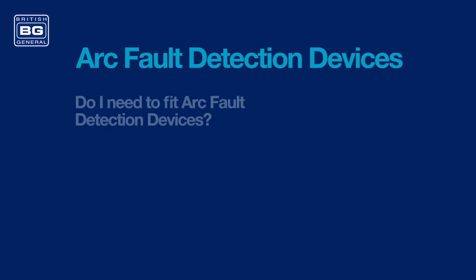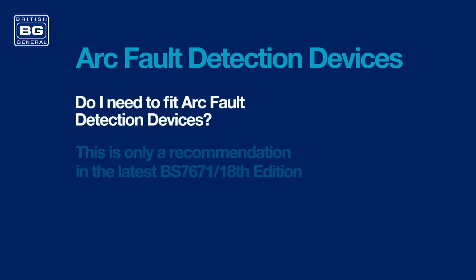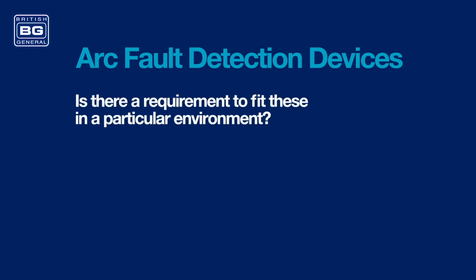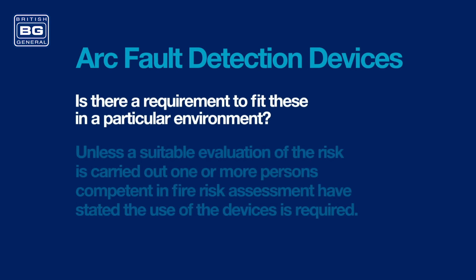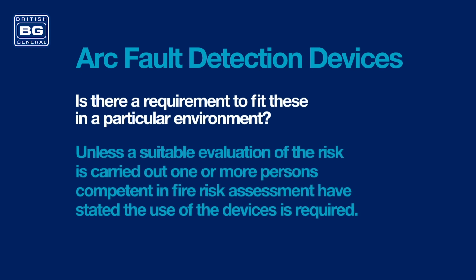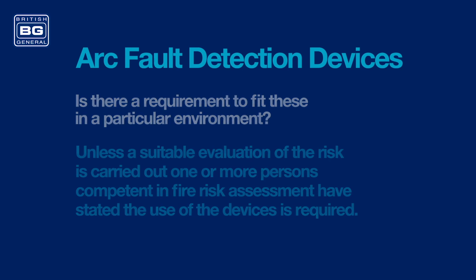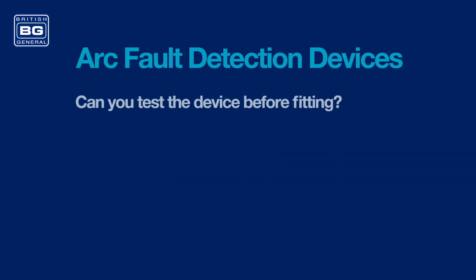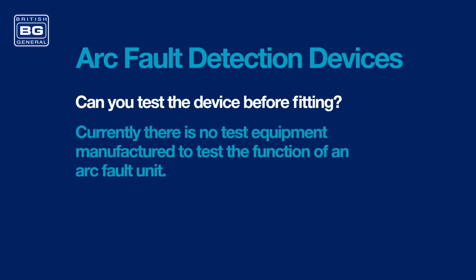Now, that is a lot of information to take in, and I'm sure you have questions. Let's look at arc fault detection devices first. Do I need to fit arc fault detection devices? This is only a recommendation in the latest BS 7671 18th edition. Is there a requirement to fit these in a particular environment? Unless a suitable evaluation of the risk has been carried out by one or more persons competent in fire risk assessment has stated the use of the devices is required. Can you test the device before fitting? Currently, there is no test equipment manufactured to test the function of an arc fault unit.